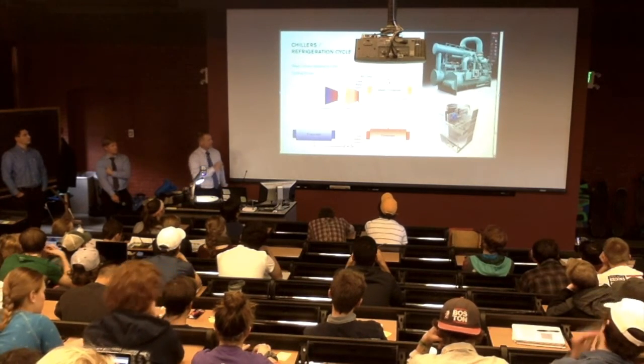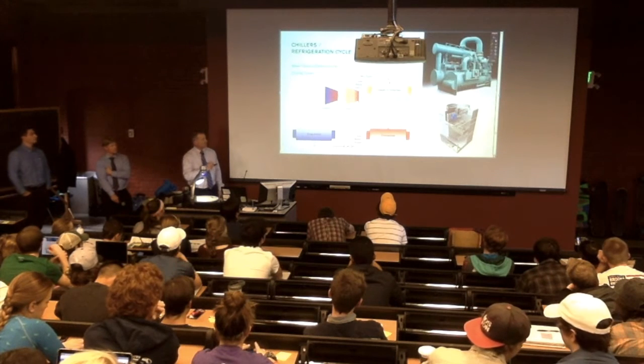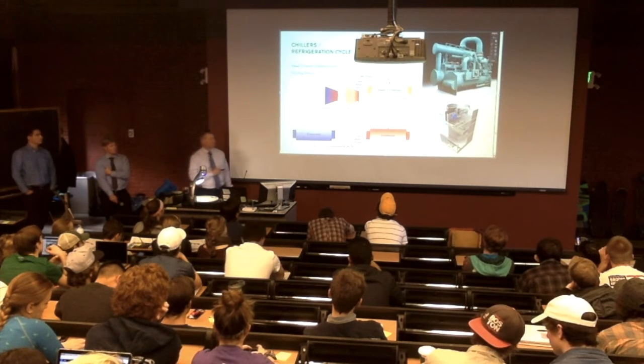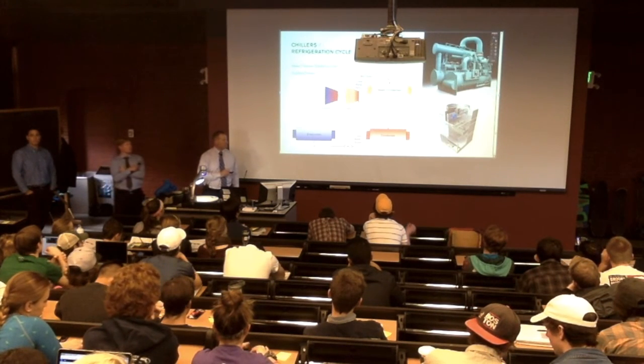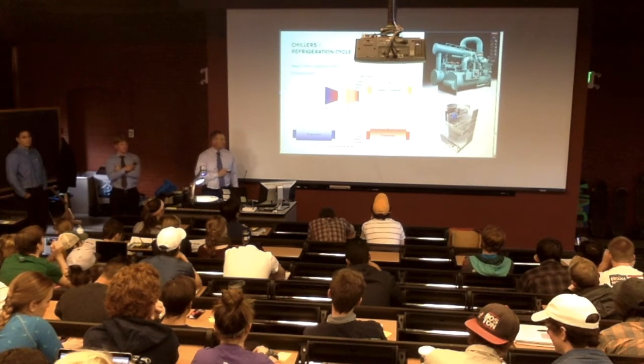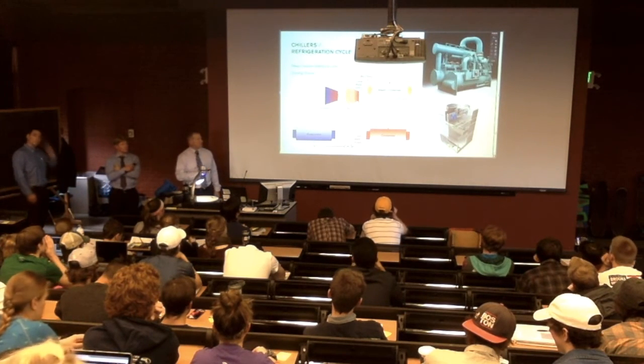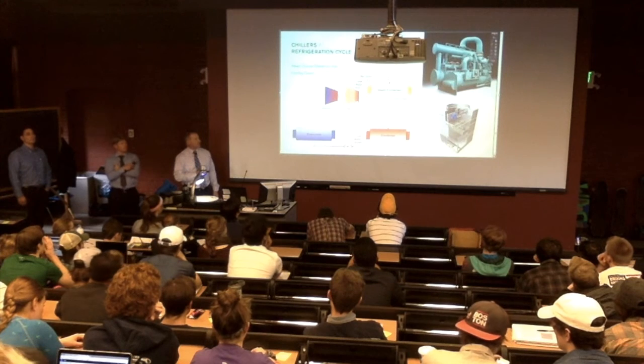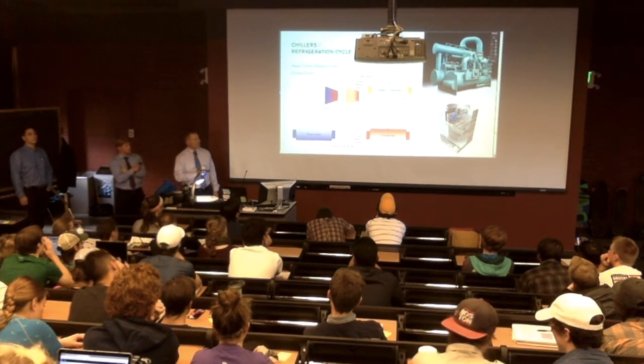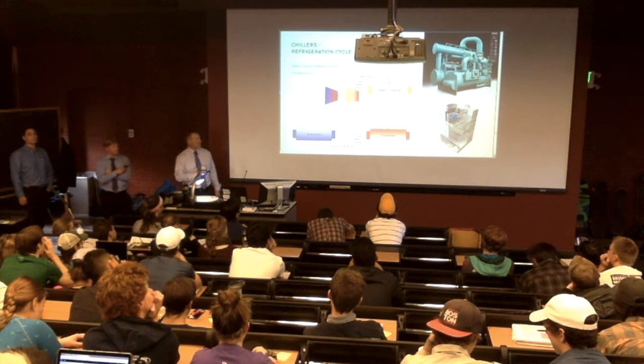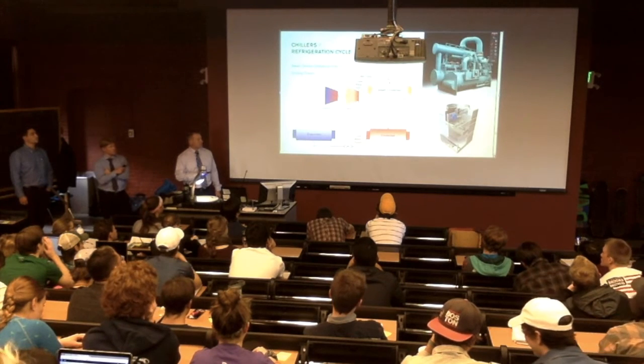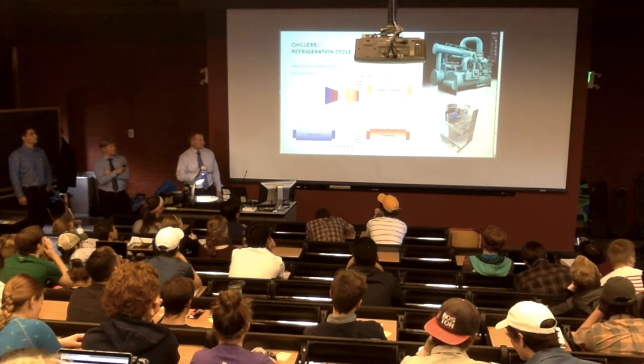You have up here a chiller. That's what it looks like. It's a huge piece of metal. It weighs probably 20,000 pounds. It has an evaporator bundle and a condenser bundle. The evaporator makes the chilled water side of things, cold water, and then the condenser bundle rejects the heat, the cooling, and it rejects it through the cooling tower.